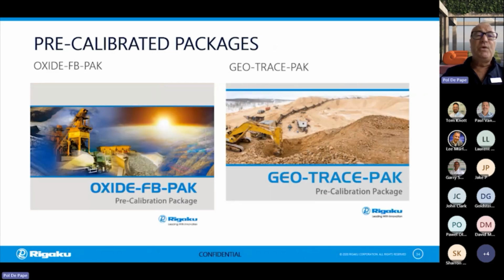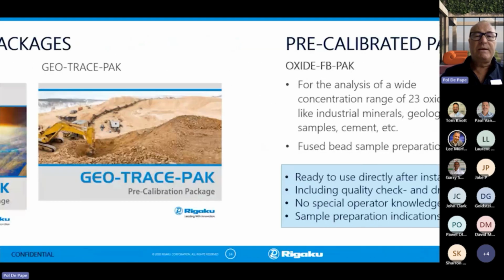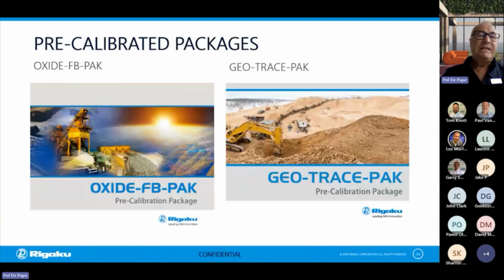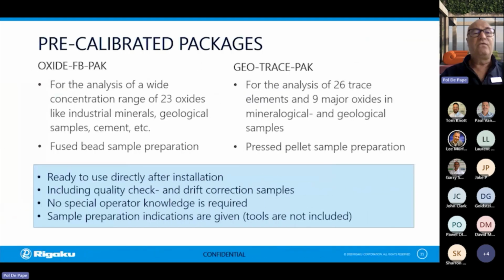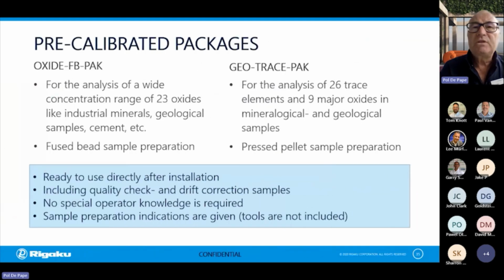Two examples of such pre-calibrated packages are the Oxide-FB-Pak and the GeoTrace pack. Both are really intended, as you may probably understand, for mineralogical and geological samples. The Oxide-FB-Pak covers 23 oxides in a very wide concentration range. The GeoTrace pack is for 26 trace elements and 9 major oxides in mineralogical and geological samples. The GeoTrace pack uses pressed pellet sample preparation, and the Oxide-FB-Pak uses fused bead sample preparation.